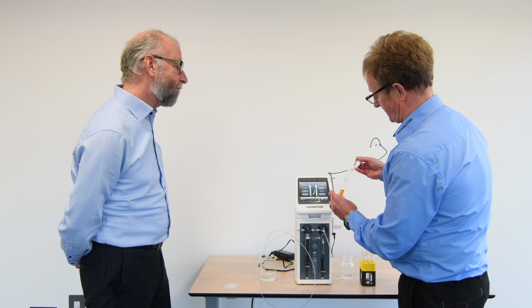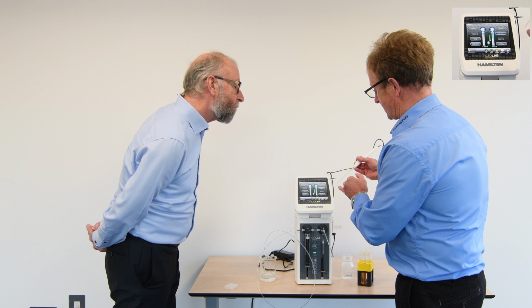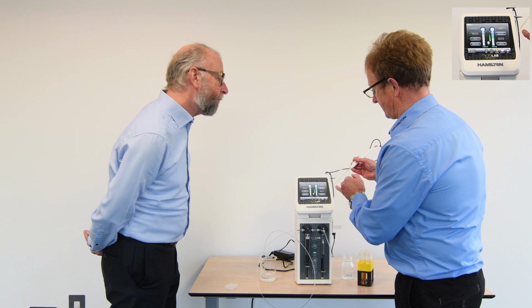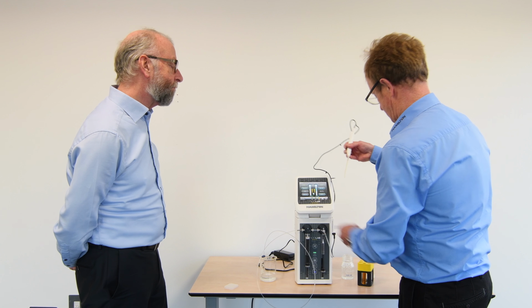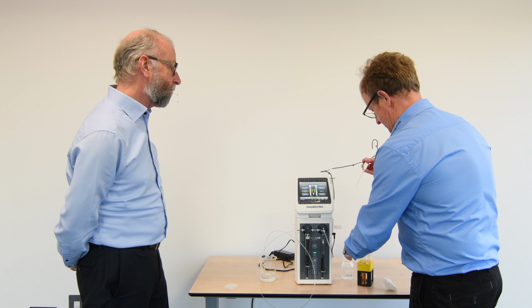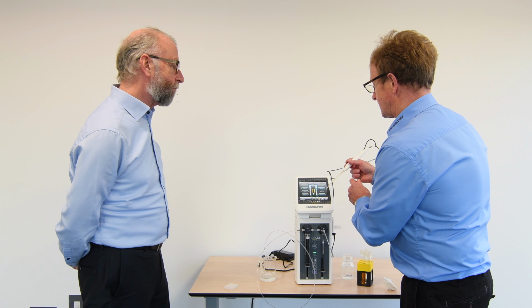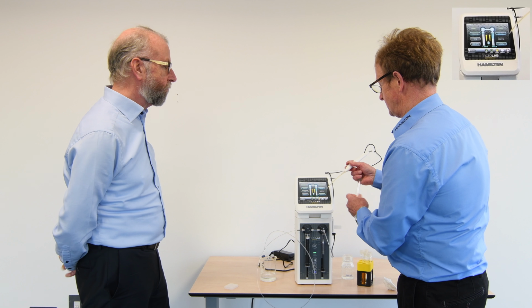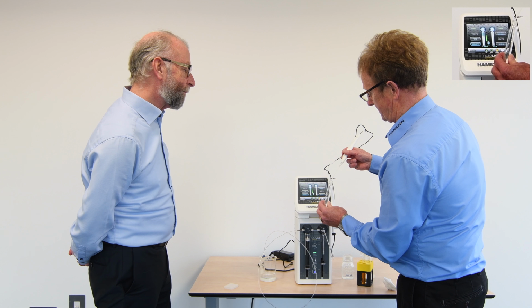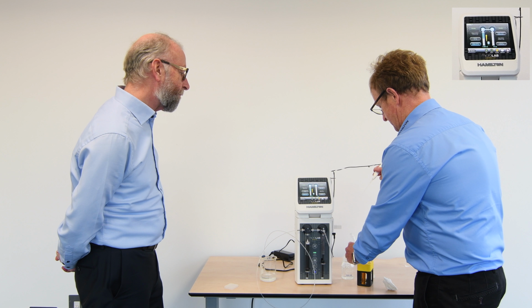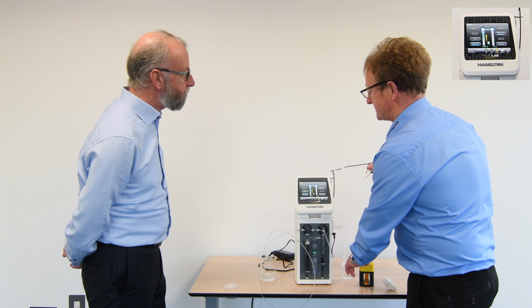Now we're still running with this particular program with an air gap mode, so the next button press is going to aspirate a small air gap. And I can now wipe my tip. Now once I've done that, we can dispense that 1 in 4 dilution into your new sample, which is done. And automatically the unit is now ready because it's aspirated an amount of material.